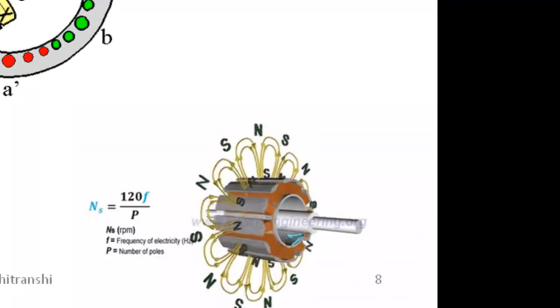Now what is a torque angle or a power angle? We can see from this graph. If the alternator is rotating like this, as seen in this figure, then ns is the synchronous speed of the magnetic field, and the rotor is rotating at a certain speed. There is an angular velocity difference between the synchronous speed of the magnetic field and the actual rotation of the rotor. We can say this is a fixed angular displacement between these two objects, and this angular displacement between the synchronous speed and the actual rotor position inside the alternator is known as the torque angle, and this torque angle reflects in the form of a power angle in a power system or in a transmission line, right?